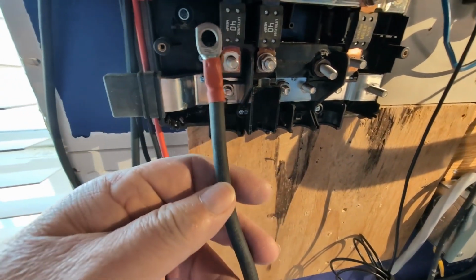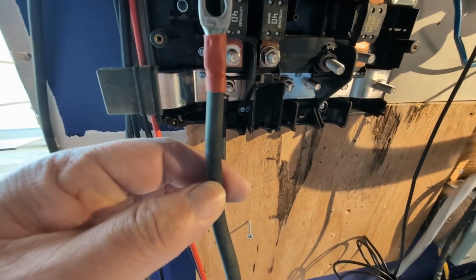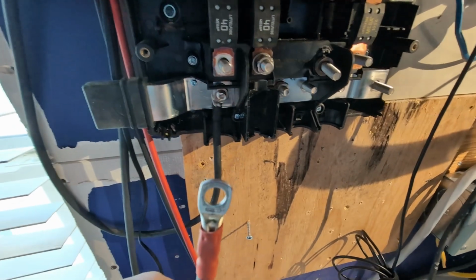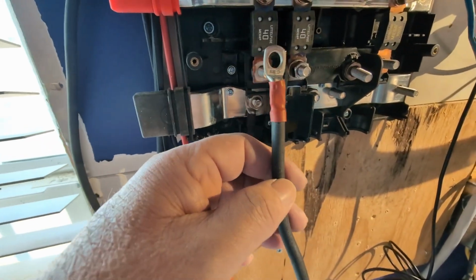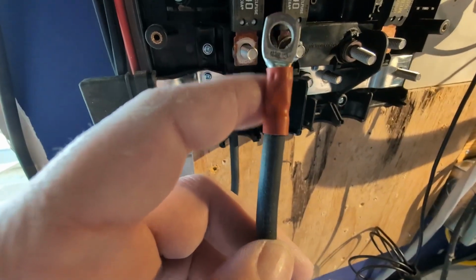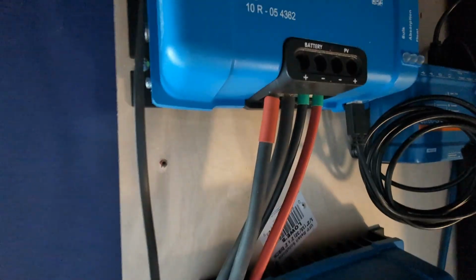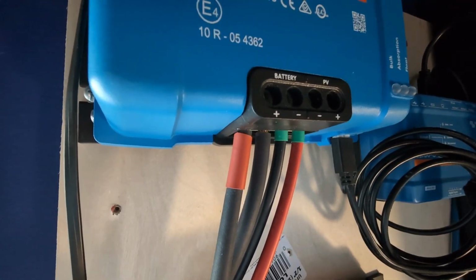So a number 8 gauge welding wire can handle 40 amps, it's not going to cause any problems. So we should be safe to go ahead. You see, even though I'm using a black wire, I wrapped it with red heat shrink so we know that's the positive side. It goes to the positive side where it says battery.